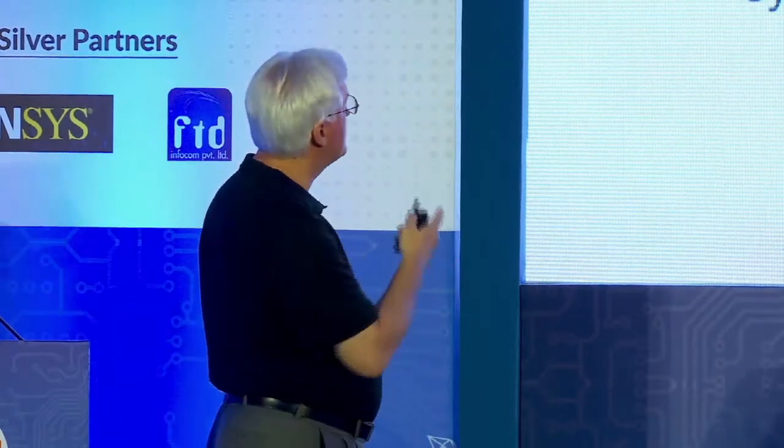There are tools that throw incorrect commands at communication ports in systems to see whether the system or the product itself will respond and still be able to function even though these garbage or incorrect commands are bombarding the communication port. So those are three aspects of it: network robustness testing, the basic functionality of the equipment, and good engineering processes. In terms of robustness testing, you may have heard this referred to as fuzz testing or penetration testing.